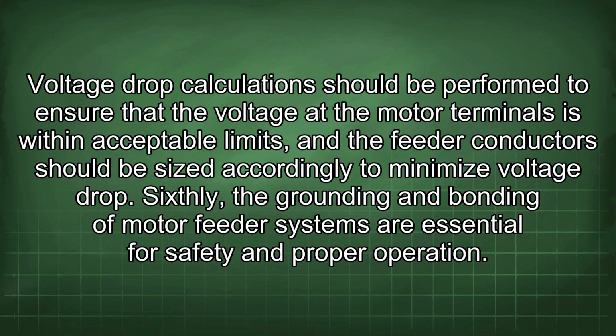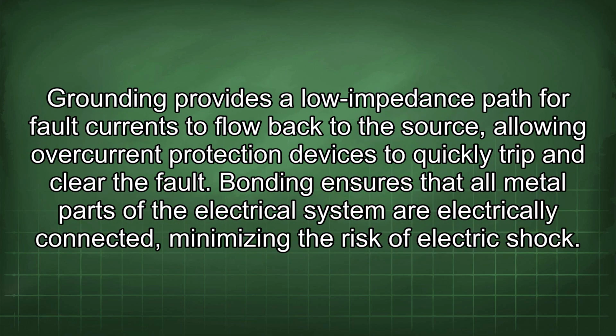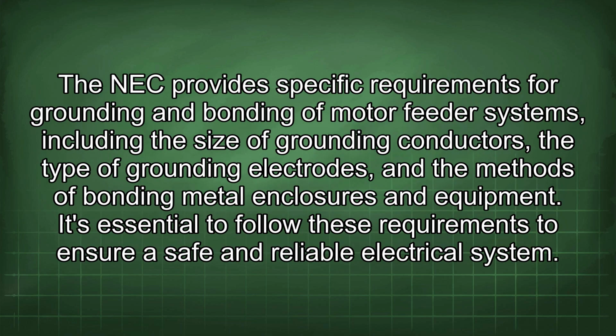Sixthly, the grounding and bonding of motor feeder systems are essential for safety and proper operation. Grounding provides a low impedance path for fault currents to flow back to the source, allowing overcurrent protection devices to quickly trip and clear the faults. Bonding ensures that all metal parts of the electrical system are electrically connected, minimizing the risk of electric shock. The NEC provides specific requirements for grounding and bonding of motor feeder systems, including the size of grounding conductors, the type of grounding electrodes, and the methods of bonding metal enclosures and equipment. It's essential to follow these requirements to ensure a safe and reliable electrical system.